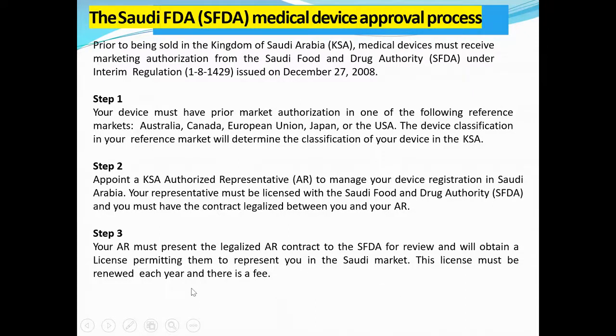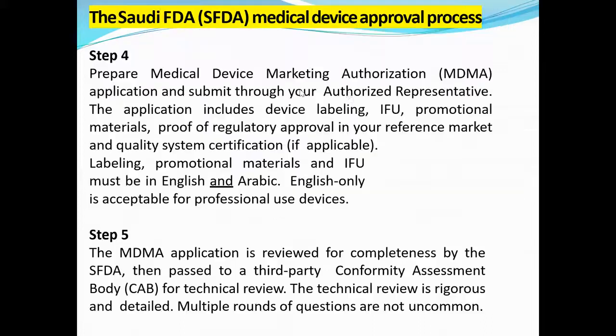The license must be renewed each year, and everywhere you have to renew the license, right? And you have to register your firm. Then prepare the medical device marketing authorization, that is MDMA, application and submit it through your authorized representative. The application includes device labeling, intended use, that is IFU, promotional material, proof of regulatory approval in your reference market, and quality system certification if applicable, that is the ISO certificate. Labeling, promotional material, and IFU must be in English and Arabic. So this is a mandatory requirement.